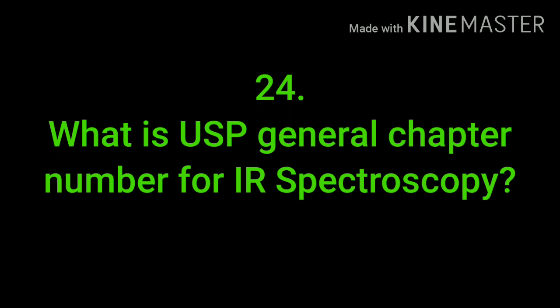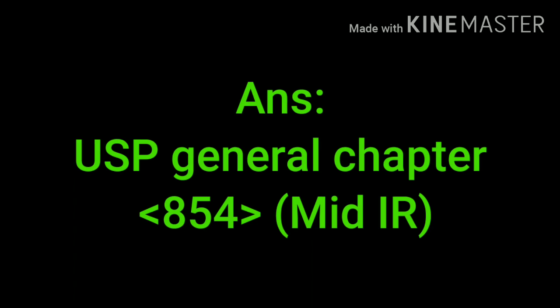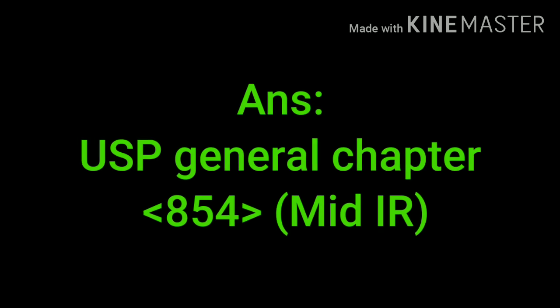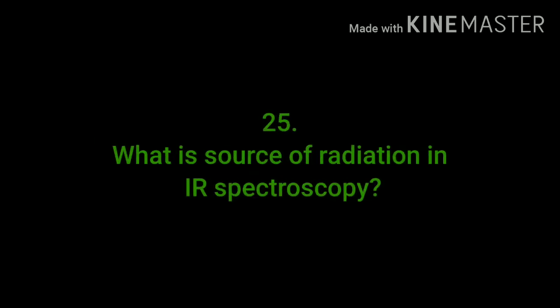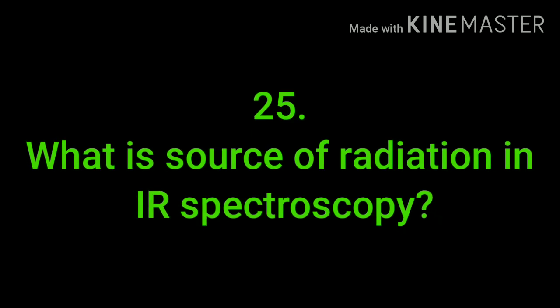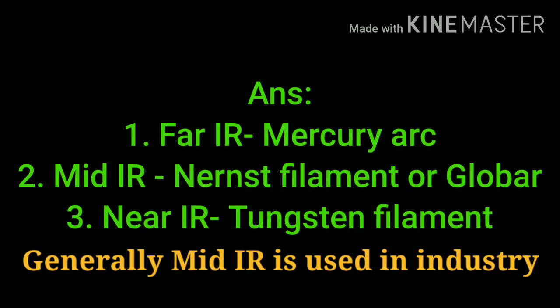What is the USP chapter number for IR spectroscopy? The USP general chapter number is 854, used for IR spectroscopy. What is the source of radiation in infrared spectroscopy? For far IR, a mercury arc source is used. For mid IR, a Nernst filament or Globar is used. For near IR, a tungsten filament is used. Generally, in the industry, mid IR is used.